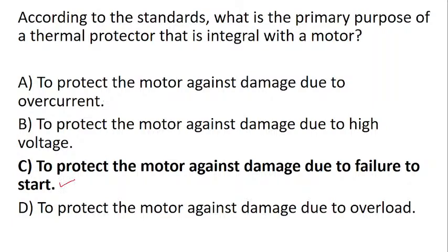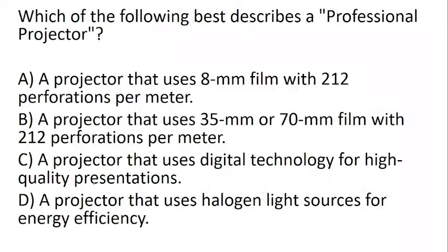No, yung nafe-fail siya start, no, hindi niya naabot yung kanyang required torque, so nag-iinit yan. So if you have a thermal protector, it will just automatically cut off the supply para hindi masunog yung winding. So that is separate to an overload protector. Yung thermal kasi is yung mismong heat, no, doon sa ating motor, yung kanyang inaano. Okay.